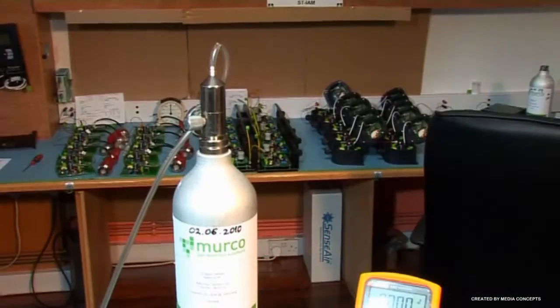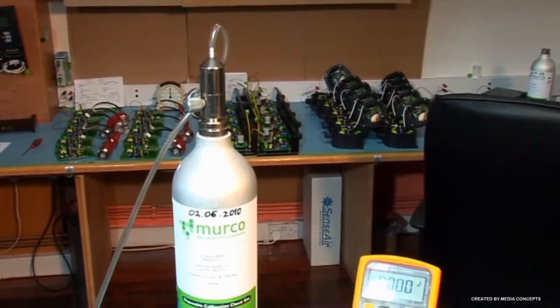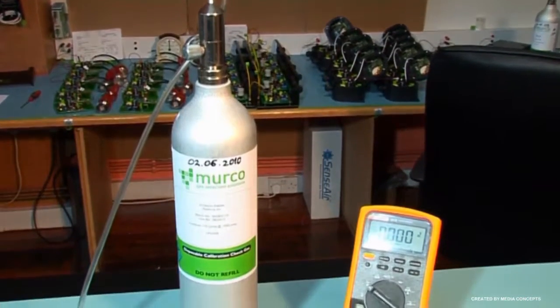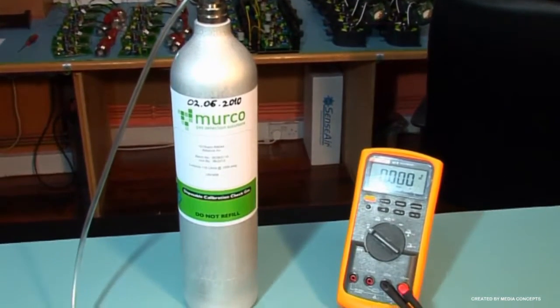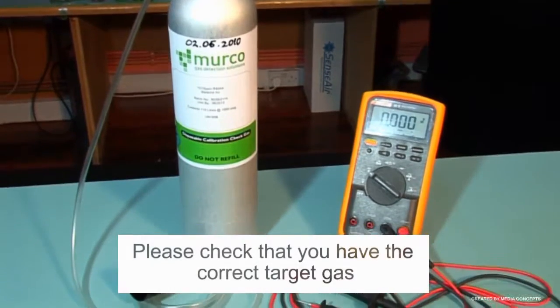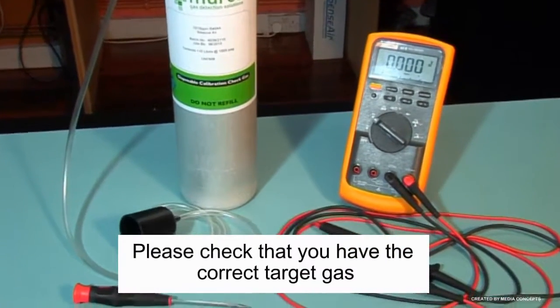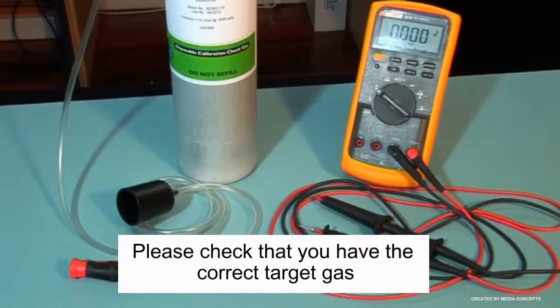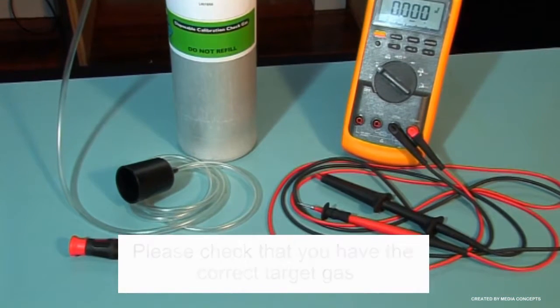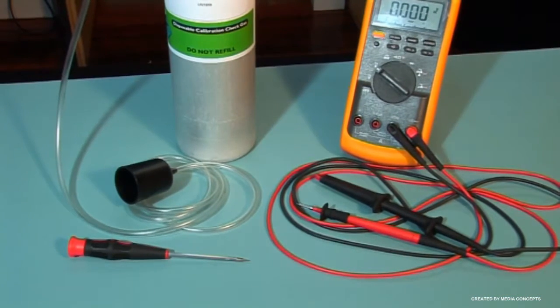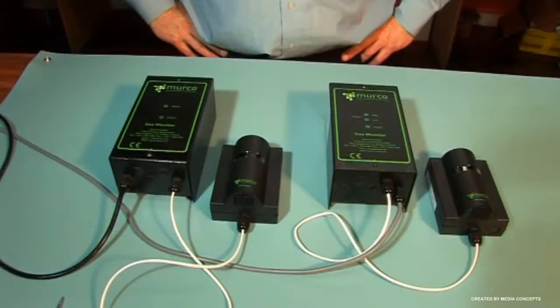The tools required are a digital voltmeter with a resolution to 2 decimal places, crocodile clips and/or a test probe, a flatbed screwdriver and a Murco calibration kit, which includes your cylinder of calibration gas, flow regulator, flexible non-absorbent tubing and a vented calibration hood.